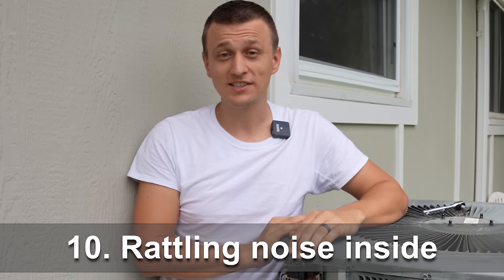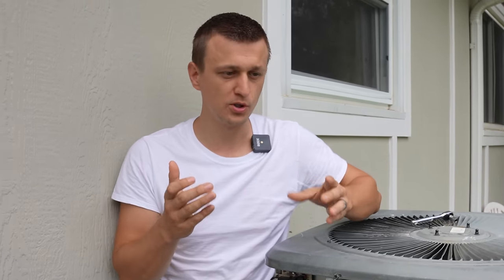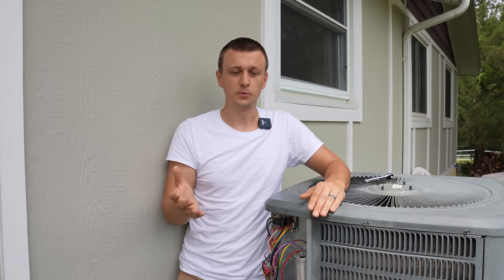And number 10, rattling noises inside. These can come in many variations and forms, and honestly, you just have to track it down. Just listen to the noise and see if you could narrow it down, where's that noise coming from? I can give you a few different examples. One call I went on, the lady was saying that her furnace is making a really loud rattling sound.